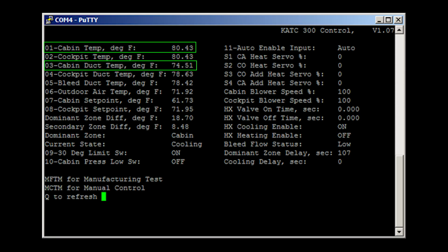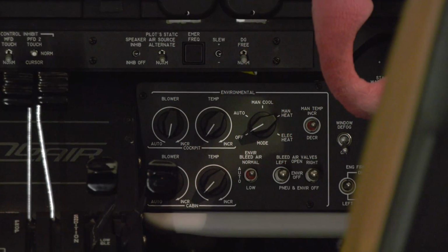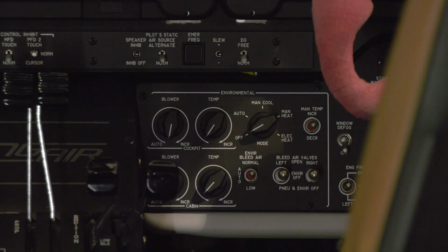Another difference to track is the difference between the zone and duct temps. If there's a huge difference between the cabin values and not much difference between the cockpit values, troubleshoot the forward evaporators or expansion valve. If there's not that much change in the cabin, look at the aft components. The bleed duct temperature sensor readings shown on the diagnostics screen can also be a quick way to check the operation of your heat exchanger bypass valves. During a ground run, the bleed air heat exchangers hold the duct temp within 15 to 20 degrees Fahrenheit of outside air temperature. With the manual controls, you can drive the valves and watch the bleed duct value change accordingly. The blower speeds show what the controller is commanding as a percentage of total speed. If the blower switch on the subpanel is set to manual, this speed shown has no meaning.